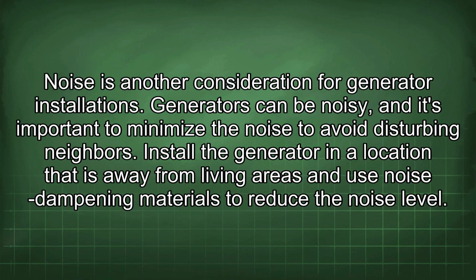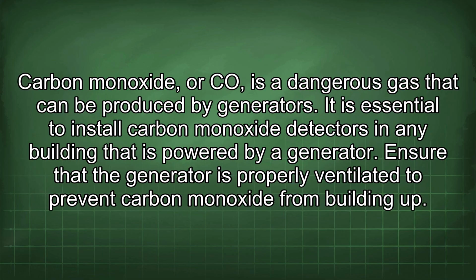Noise is another consideration for generator installations. Generators can be noisy, and it's important to minimize the noise to avoid disturbing neighbors. Install the generator in a location that is away from living areas and use noise-dampening materials to reduce the noise level. Carbon monoxide, or CO, is a dangerous gas that can be produced by generators. It is essential to install carbon monoxide detectors in any building that is powered by a generator. Ensure that the generator is properly ventilated to prevent carbon monoxide from building up.